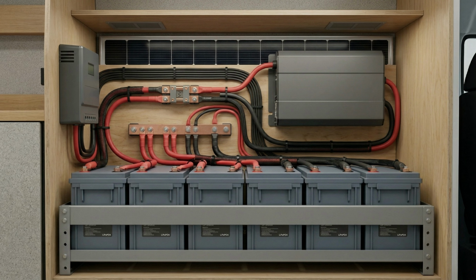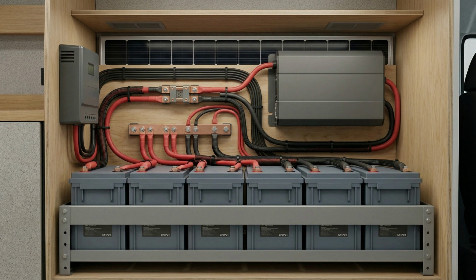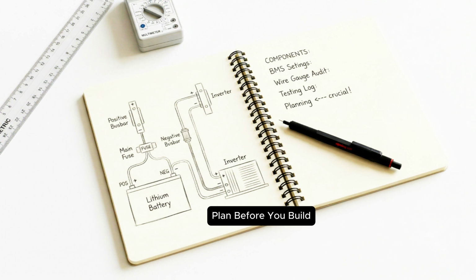Connecting positive to negative can destroy sensitive components such as your inverter, your charge controller, or your battery management system. Modern electronics usually do not forgive polarity errors. The good news is that this mistake is very preventable. Label every cable clearly. Use red and black heat shrink. Keep your layout organized. And before making the final connection, verify polarity with a multimeter. That simple 30-second check can save you from a very expensive repair.